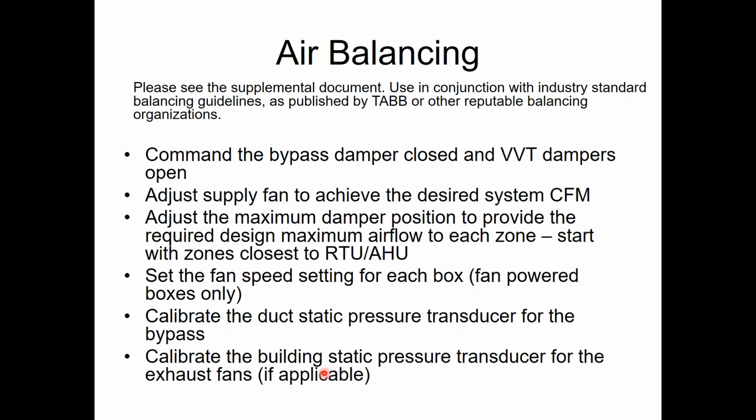Air balancing does need a little bit of discussion. So I can send this to anybody who wants this, but this is kind of the sequence of what needs to happen when you do the air balancing. Literally, I took this off of my cheat sheet from 20 years ago that I used to hand to the contractors and say, give this to your air balancer. Tell him I'll meet him on the job site. We got to do this together. I don't have the equipment to measure stuff. He doesn't have the knowledge of how to manipulate the system. We got to go on the job at the same time. Give him this sheet, right?